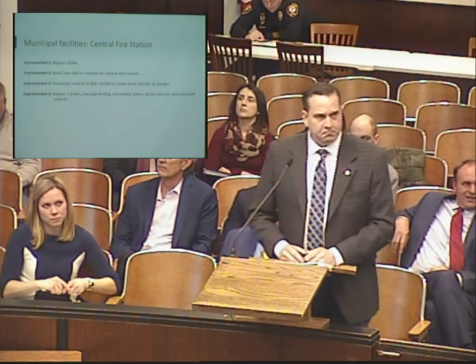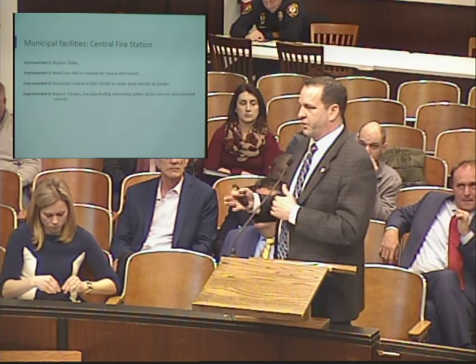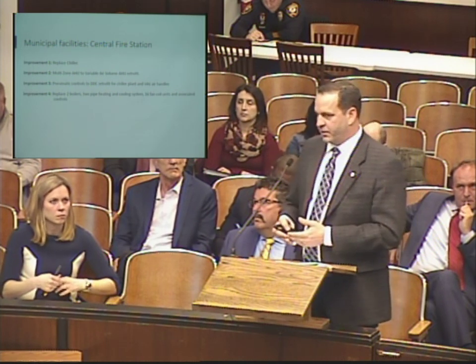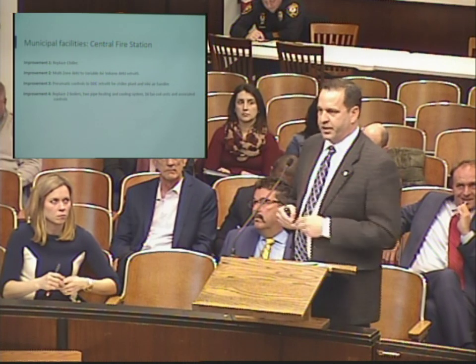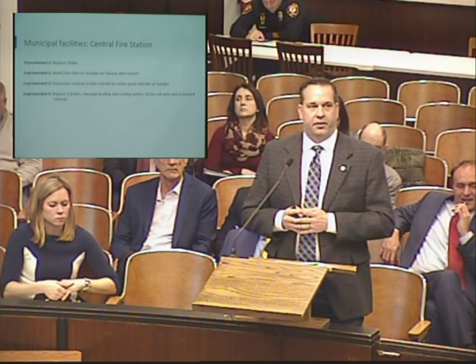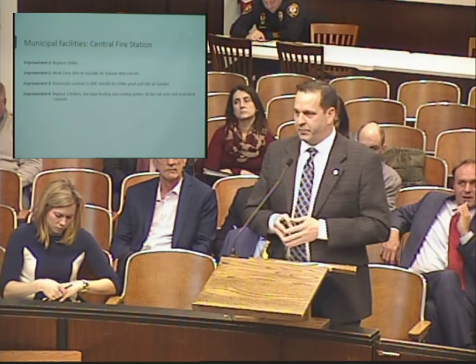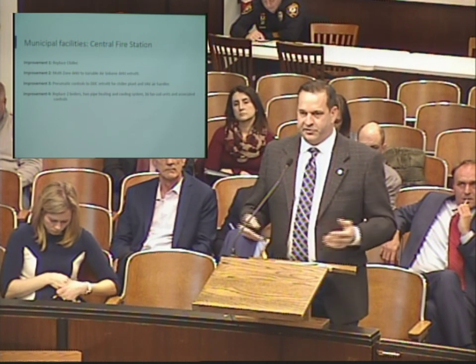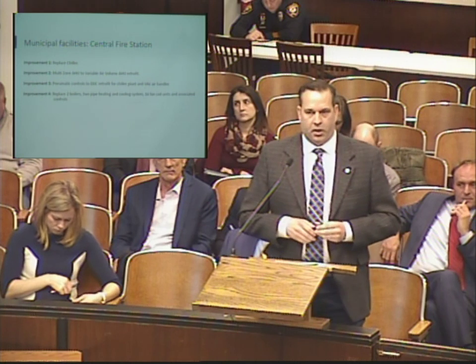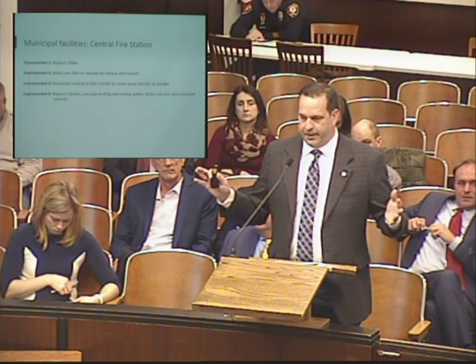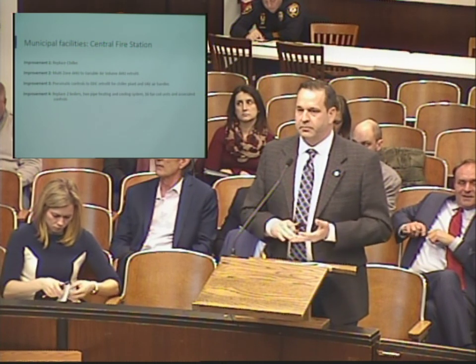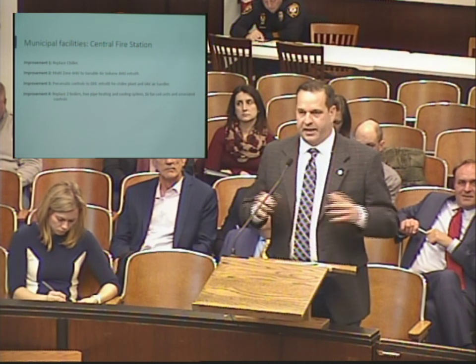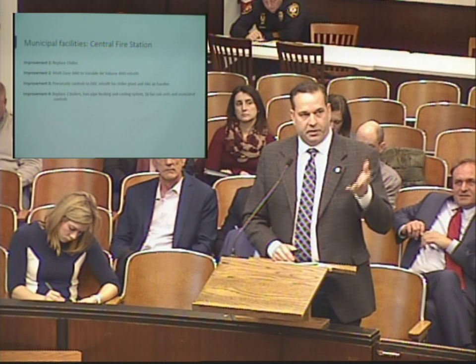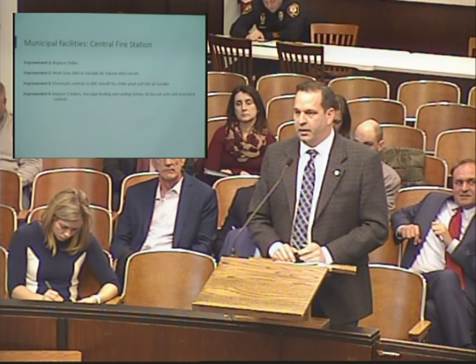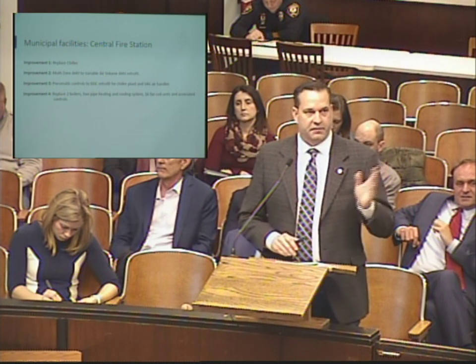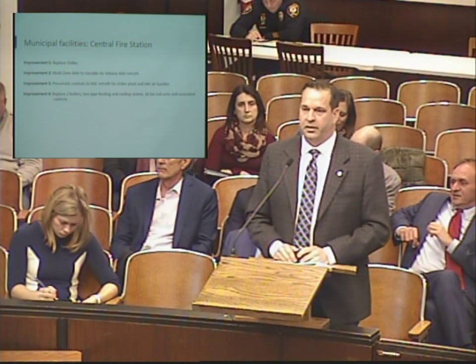Central Fire Station. I want to correct my colleague here. He was saying chillers are failing because of the water treatment. That's true, but the boilers that they have there are roughly 10 years old. They are an 80% boiler efficiency, and they're not done with their typical lifespan, but because of the poor water treatment throughout the last 10 years, it's degrading the heat exchangers in the boilers. Along with the piping in the building and all of the fan coil units, it's full of iron and bacteria buildups, different things like that. So obviously, if we replace all this equipment, water treatment is very important to maintain and prevent this from happening. Not that it was neglected, it was just probably a lack of forethought.